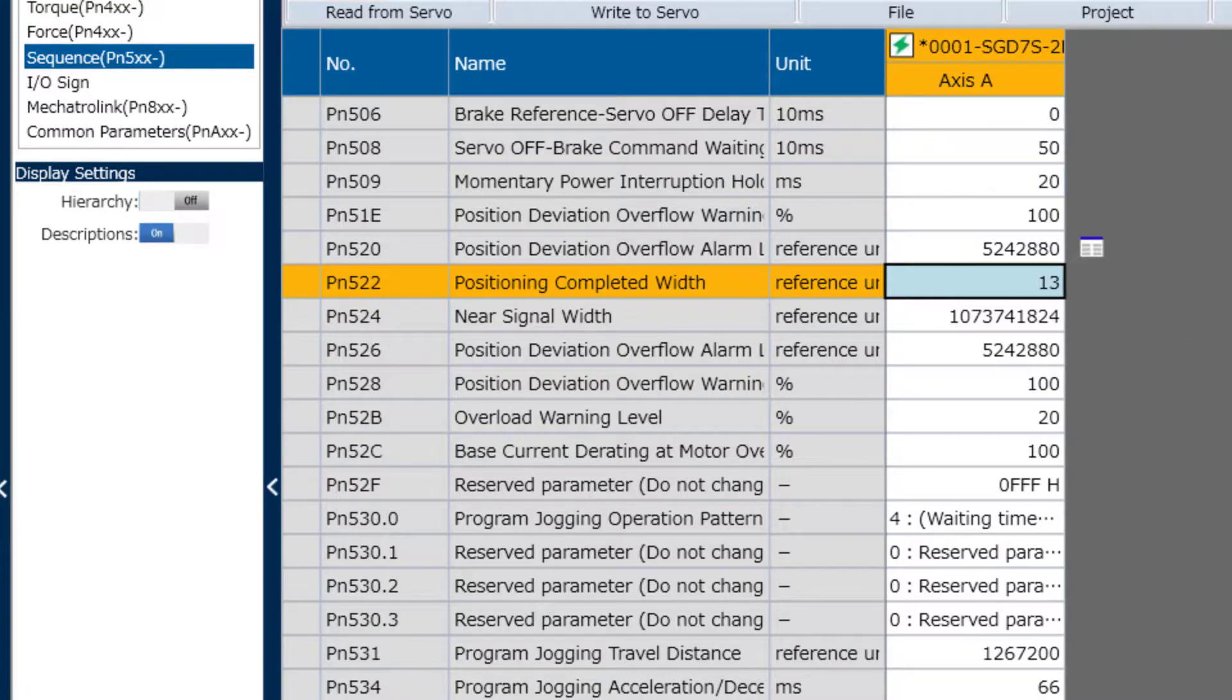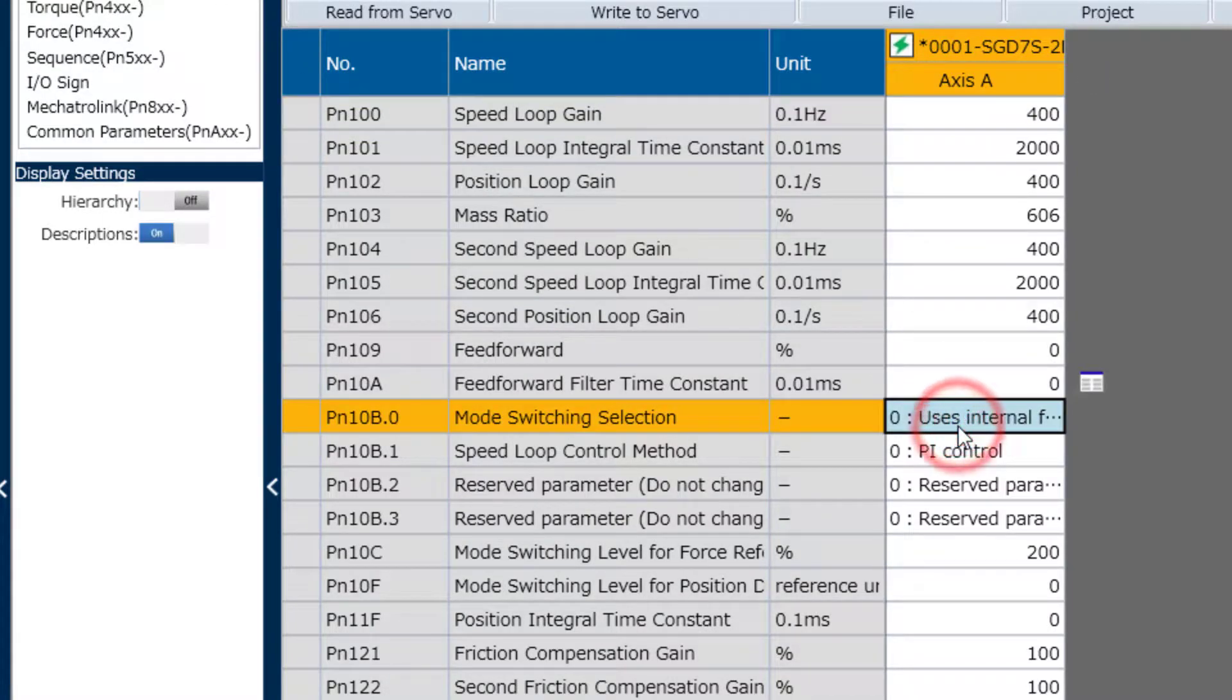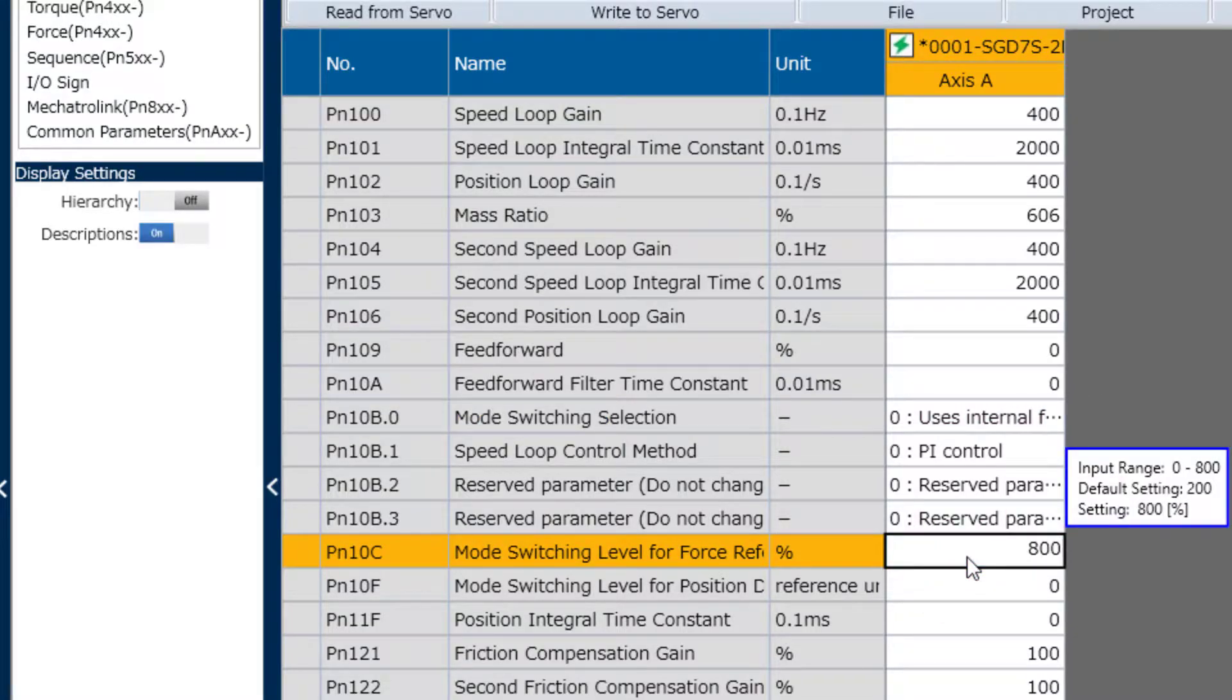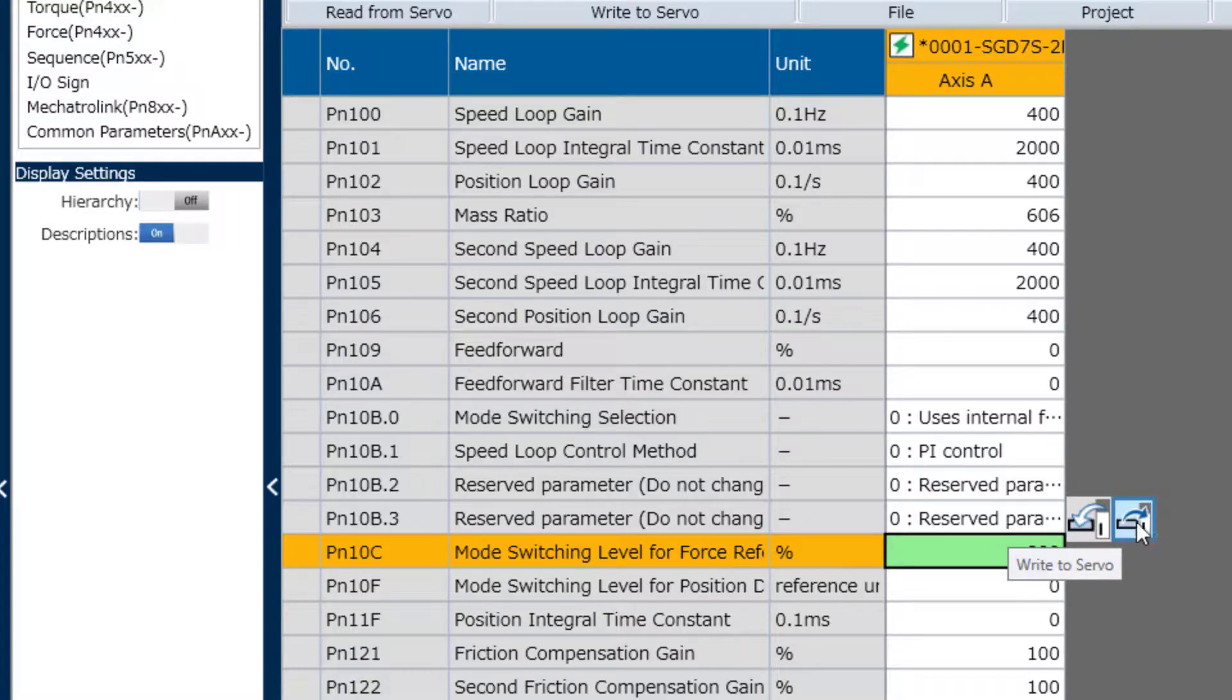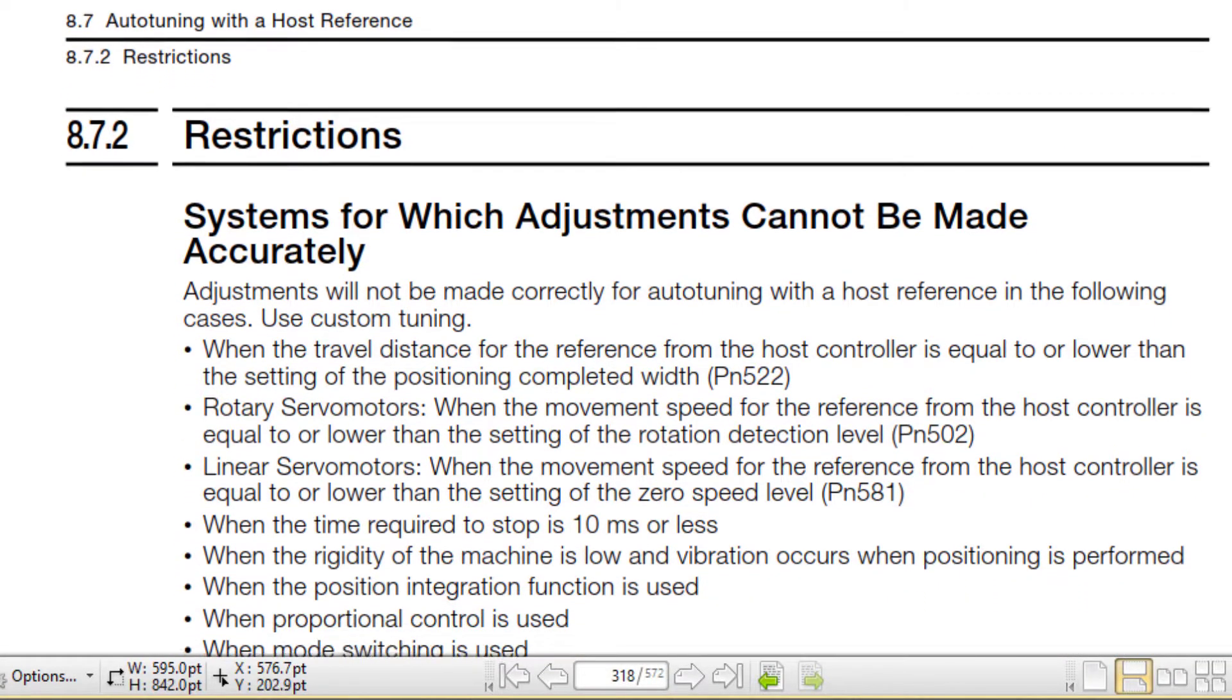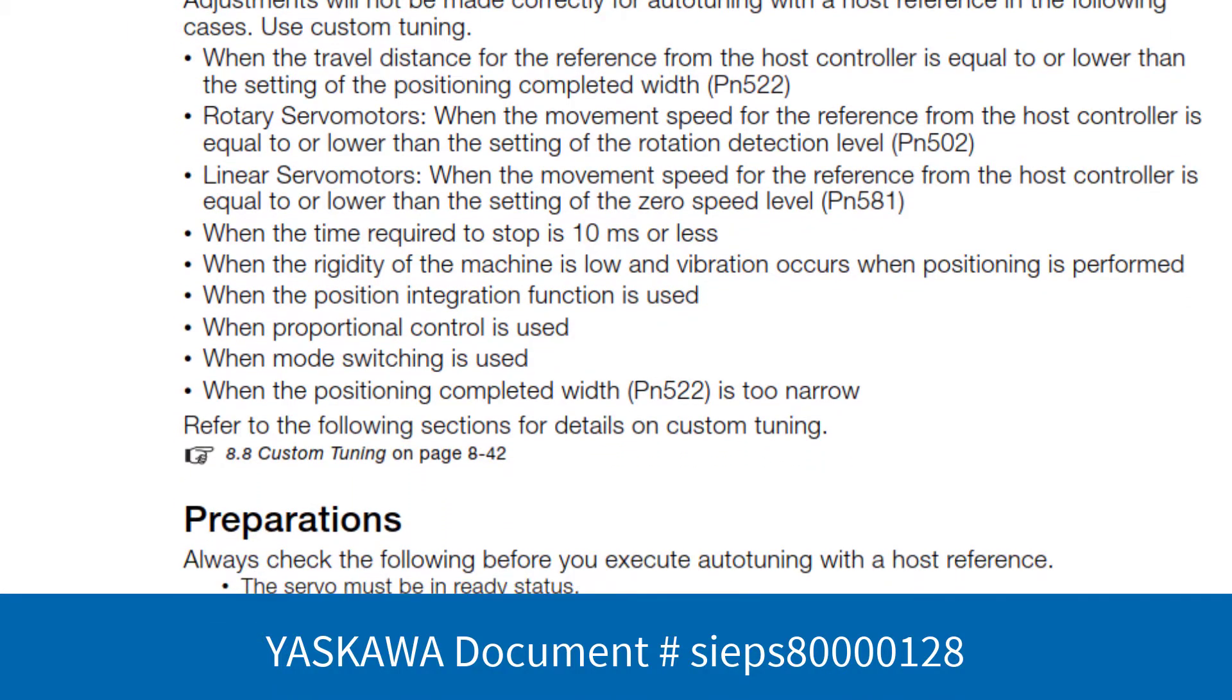It's also recommended to turn off mode switch by raising the torque level to max, which is 800%, beyond the capacity of the motor, and write that in. And in fact, there are a number of preliminary checks for auto-tuning listed in the manual.